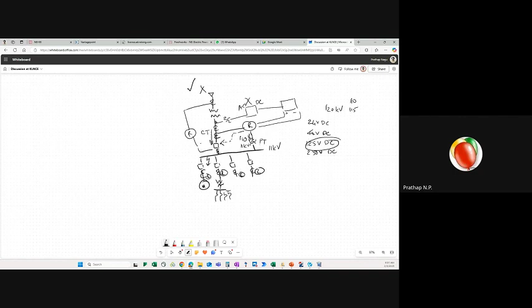If you take a giant substation, you'll add up a lot of control cables, and that's a lot of copper control cables, and copper is costly. With this technology, equivalent to 61850, everything is converted to fiber. If you look at this merging unit, you have CTs. Let me see if I can draw this.